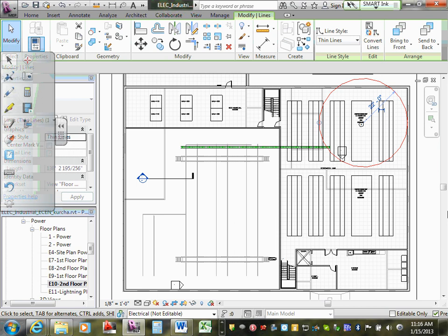Yeah, the NFPA spacing you've got is 30 by 30, 900 square feet. Yeah, I see. So instead, you've got 22 feet, okay, so there's one here. If this were to be a 30 foot radius, you have nothing over here and one smoke detector over here, and that wouldn't cover the whole area. So what we do is we move this over, so these overlapping circles are going to cover every area. And typically, if 30 feet puts us right at the ceiling, we'll move it in 4 feet all the way up.